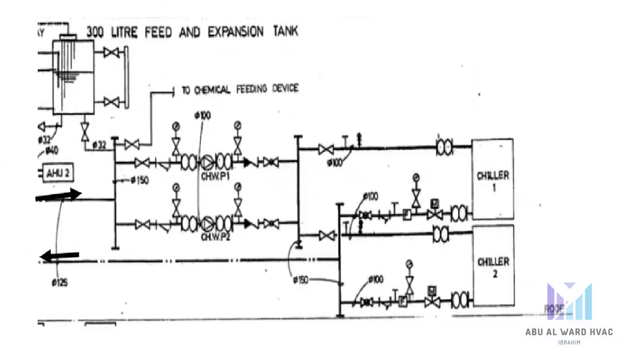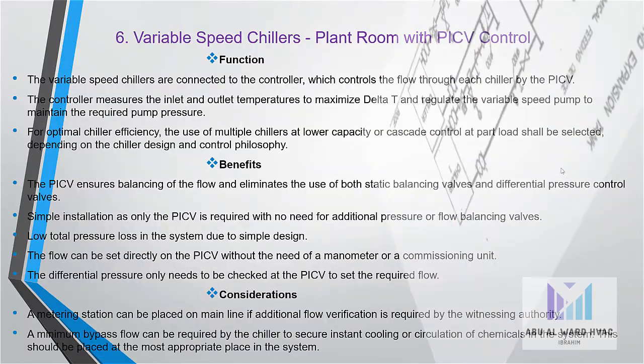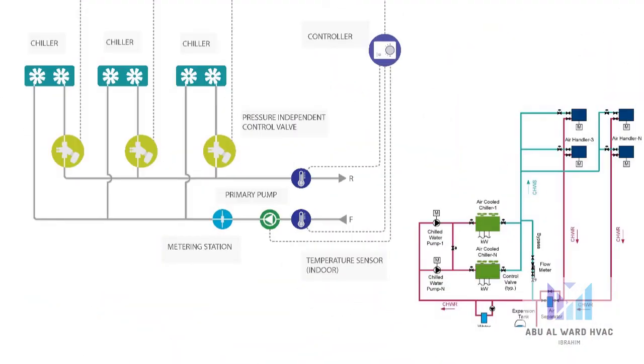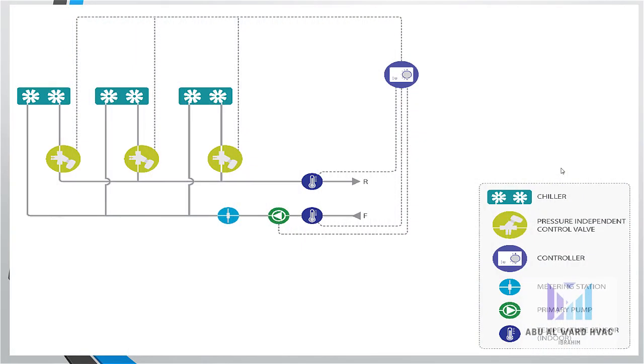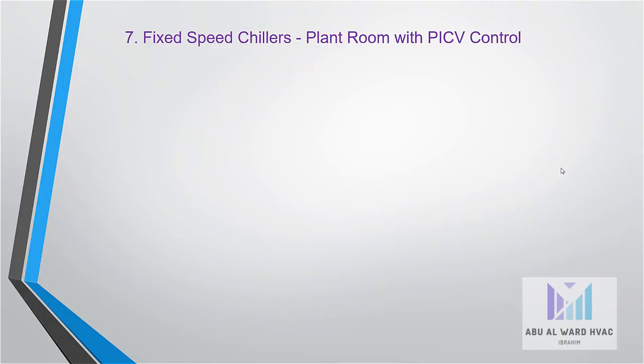Considerations: a metering station can be placed on the main line if additional flow verification is required by the witnessing authority. A minimum bypass flow can be required by the chiller to secure instant cooling or circulating of chemicals in the system. This should be placed at the most appropriate place in the system. And here is the schematic for this case.